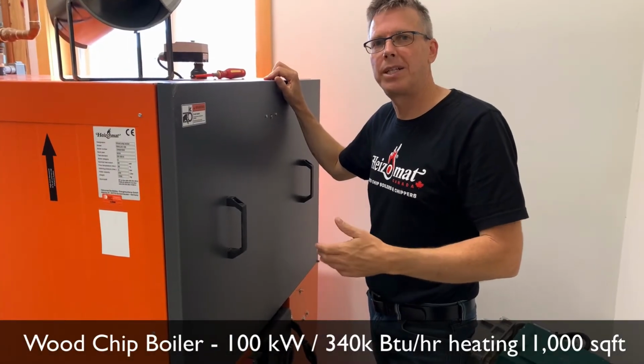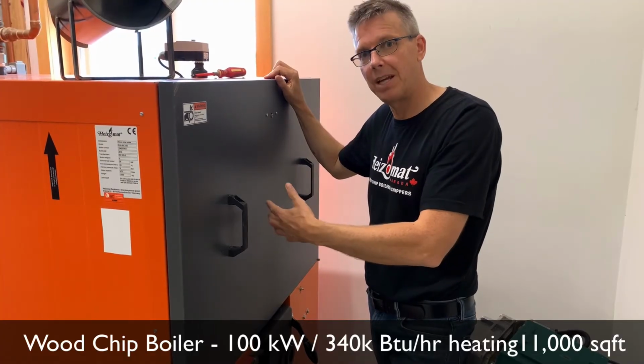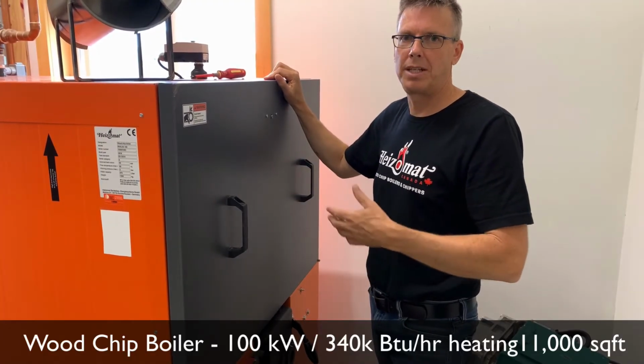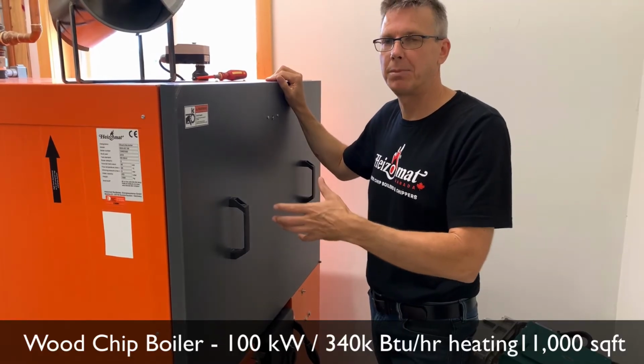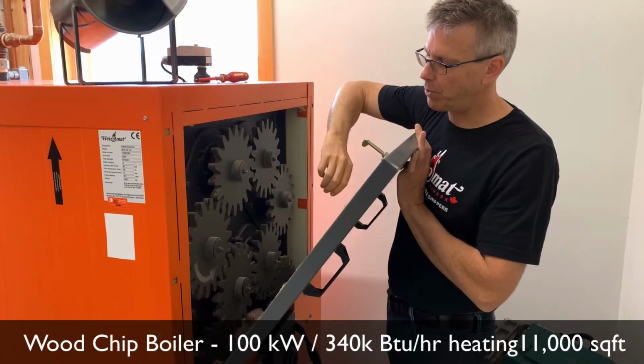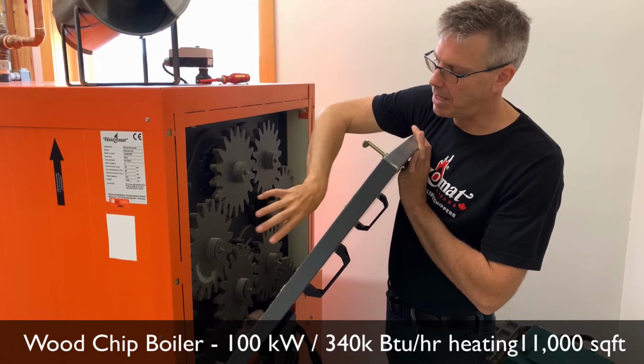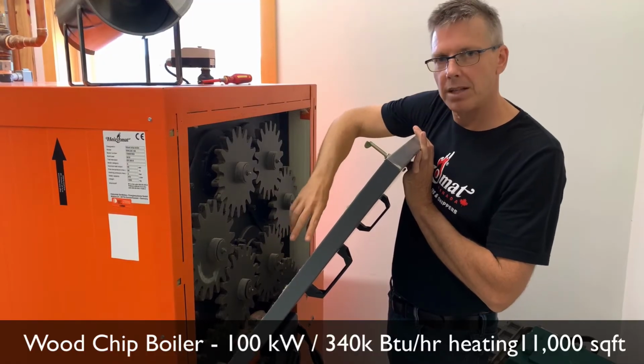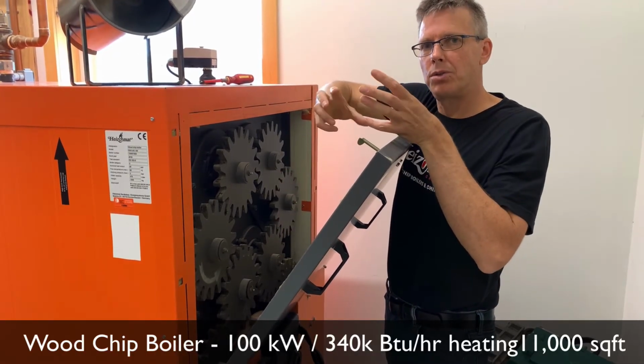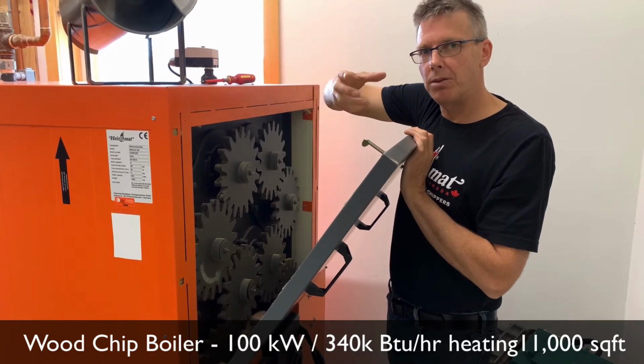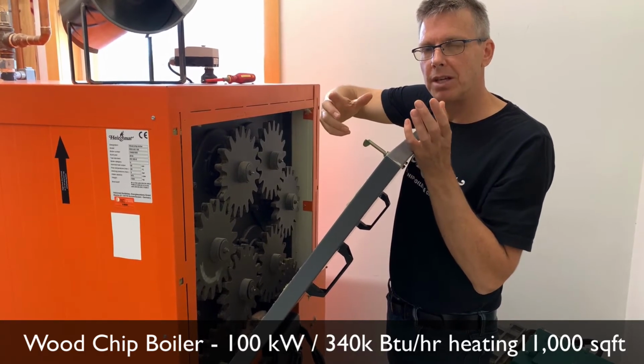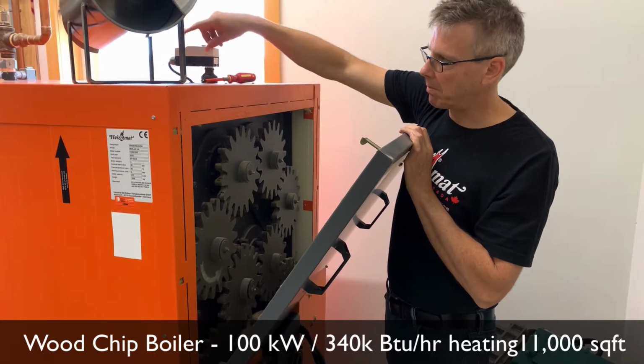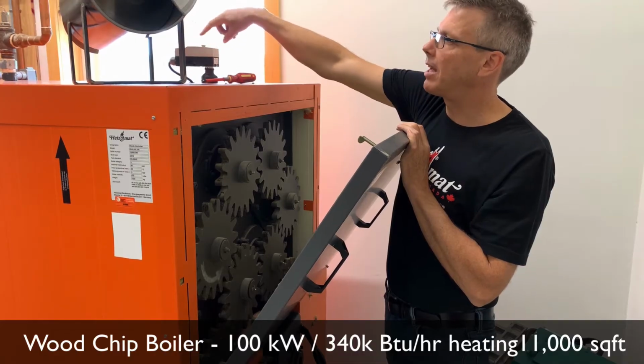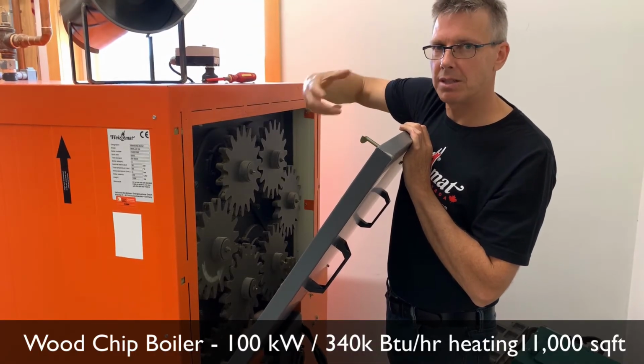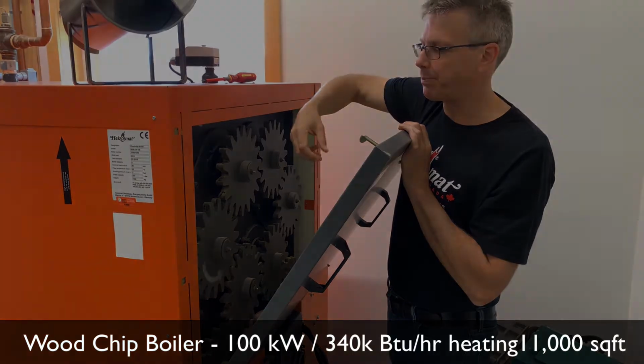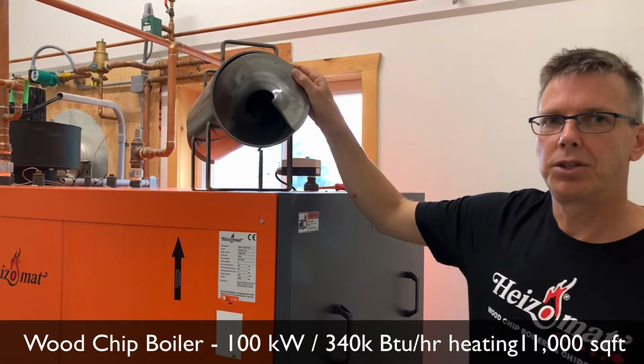So in addition to the primary de-ashing system in the fire chamber that removes the main ash from the fire, we also have a system for cleaning the heat exchanger tubes so that you never have to get in there and brush them out. For this boiler system, we actually use an auger system, and in each of the heat exchanger tubes is an auger, and that auger is designed so that when it turns, it will scrape the insides of the tubes and remove the ash from the walls to keep the efficiency up. That ash is deposited by the augers at the end of the boiler and into the ash removal system, that same ash removal system as the fire chamber. This is actually an example here of the heat exchanger tube with the auger in it.